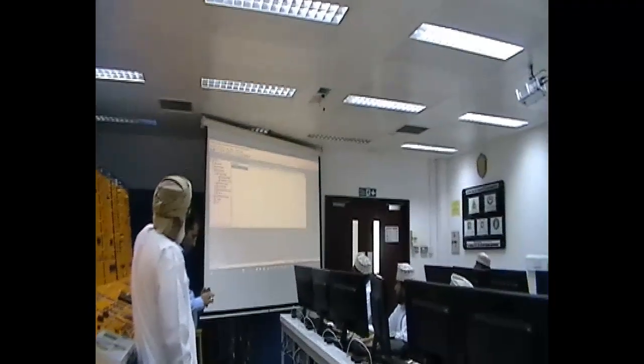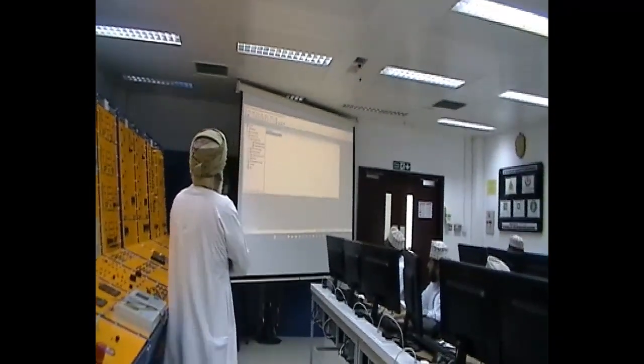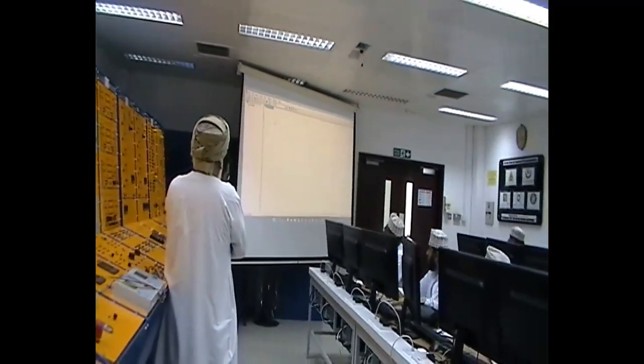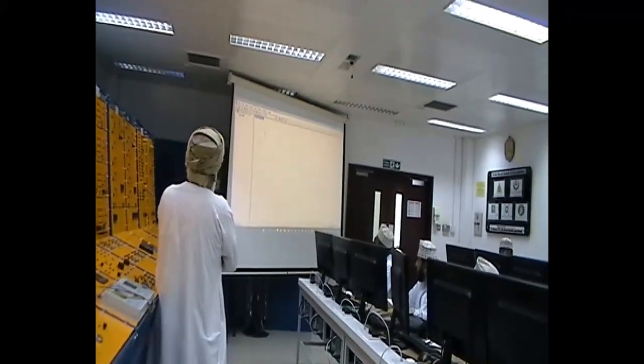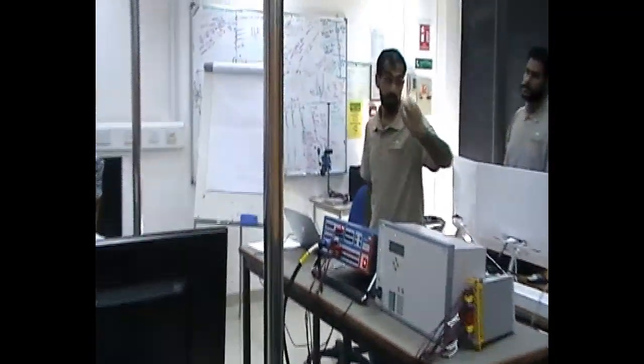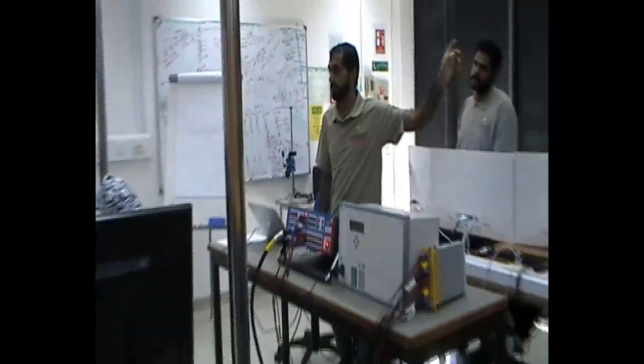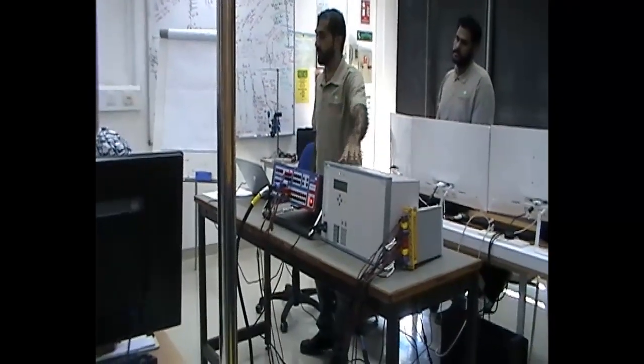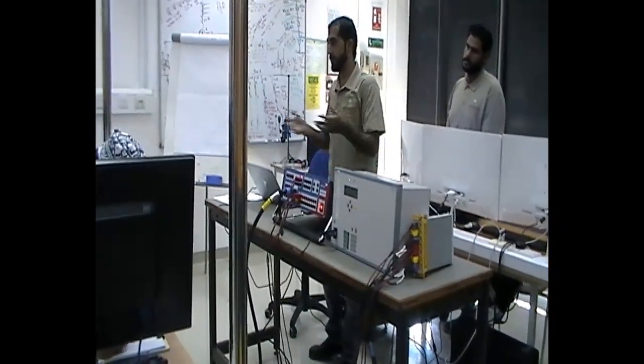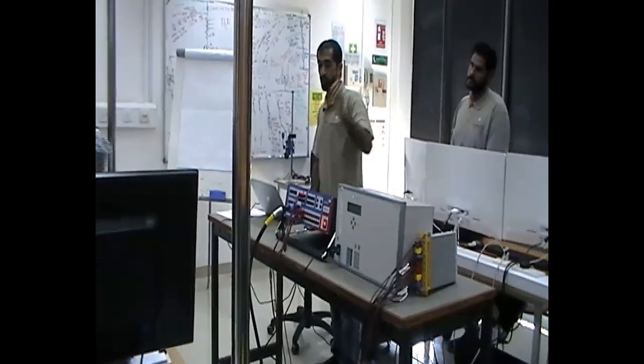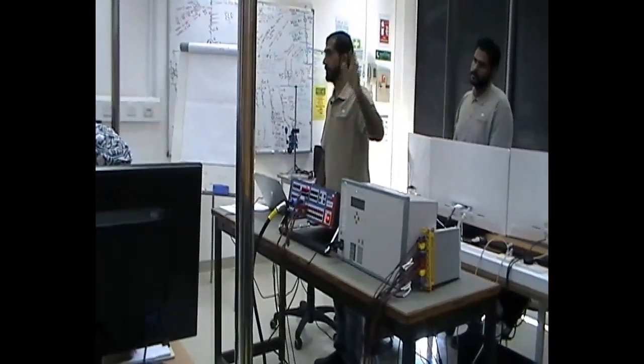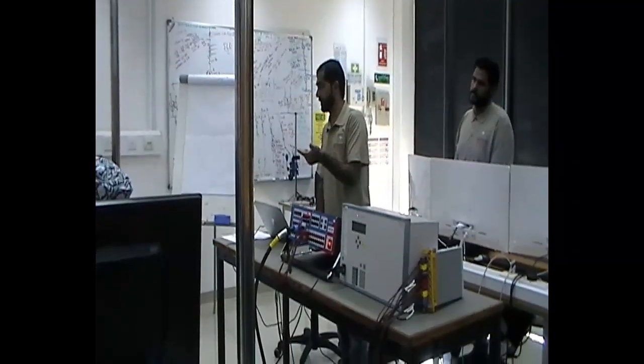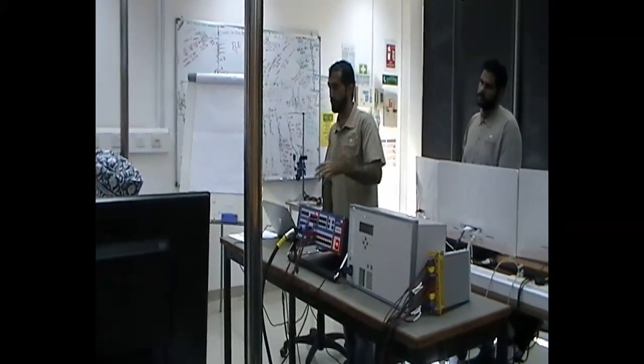I'll go through the relay first, communication. Once the relay is on, I can communicate with it through different software. Each manufacturer will have its own software. For example, here for Siemens we have DIGSI 4, and for the newer Siemens relays we have DIGSI 5. This series they call it version 4, the other they call version 5. It's just different manufacturing, but each relay type, for example all Siemens relays, usually will have one or two softwares, and ABB, we also have different softwares.